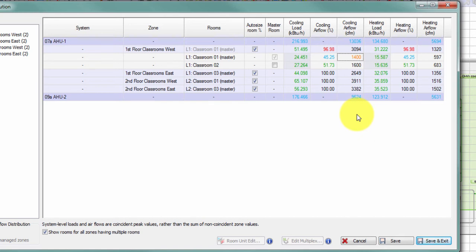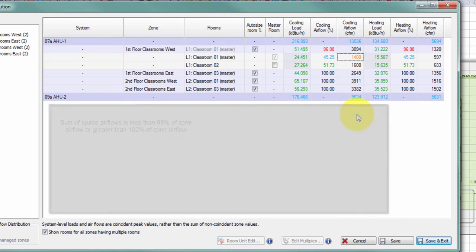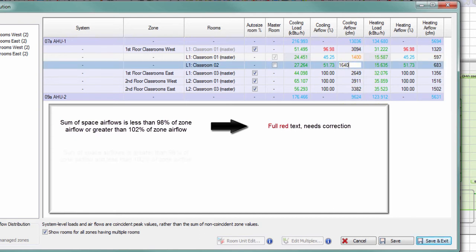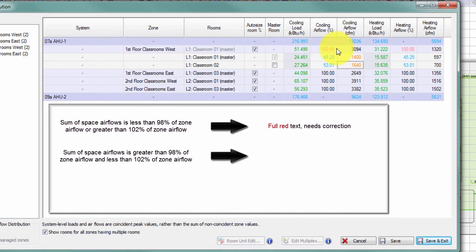The 96.98% percentage text turns red because it no longer adds up to 100%. If the sum of airflow to all spaces within a zone is not 100% of the airflow supplied to that zone, the text appears in red. There is a tolerance — if I change classroom 2 to 1640, the cooling airflow percentage displays as 100% but in light red, indicating I'm more than half a percent off but within 2%. If I were outside of 2% — less than 98% or greater than 102% — the text appears in dark red, indicating I need to rebalance.